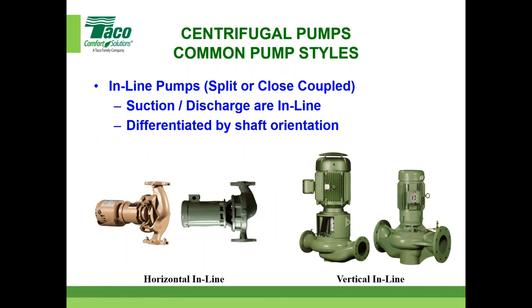Nowadays, there are other styles of common pumps. We call them verticals. We call them inline pumps, horizontal and vertical, and they're differentiated by shaft orientation. So even though the piping is vertical, these are called horizontal because of the shaft orientation. The piping is horizontal, but the shaft orientation defines these as vertical. So just keep that in mind.